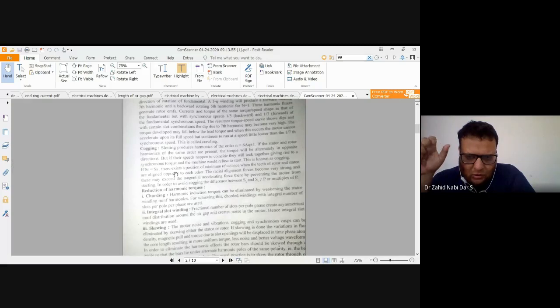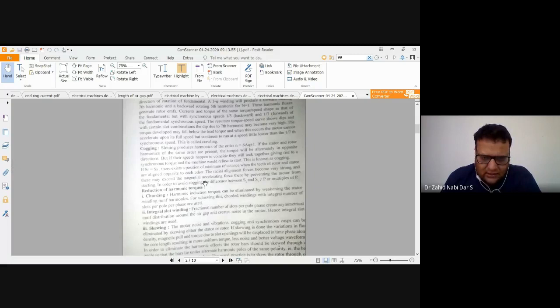Now, to avoid cogging, see how it happens. If your rotor slots SR are equal to your stator slots SS, there exists a position of minimum reluctance when the teeth of rotor and stator are aligned opposite to each other. The radial forces become very strong, and these may exceed the tangential accelerating force, thereby preventing the motor from starting. In order to avoid cogging, the difference between the stator slots and rotor slots should not be equal, and should not be multiples of poles. That means should not be equal, so some mistake in the book has happened.